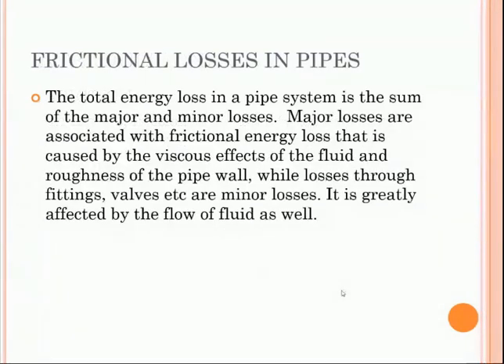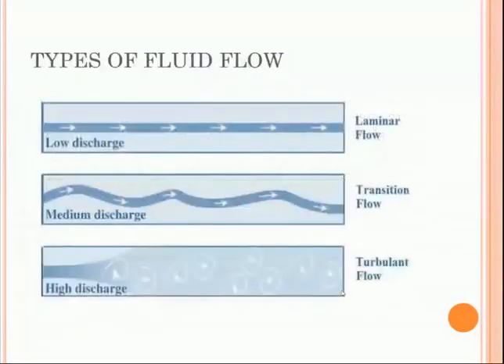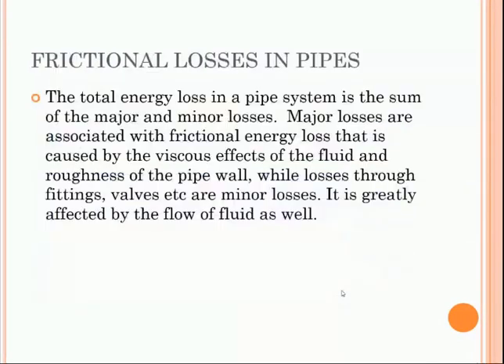This pressure loss in pipes is known as head loss, which is the sum of major losses and minor losses. Major losses are associated with frictional energy caused by the viscous effect and roughness of the pipe. Minor losses are due to expansion and contraction in diameter — because of variation in diameter, variation in velocity and pressure occurs, which causes the minor losses.